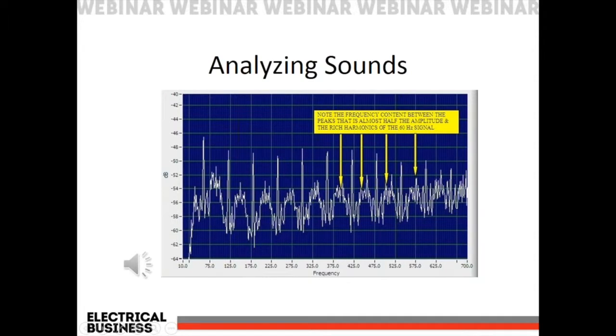Now, I hope that came through clearly, but it was a very obvious, consistent frying bacon sound that's being heard there. And when we record this on our instruments, we bring it back into a spectral analysis, in this case an FFT, or fast Fourier transform for the long version. What we're seeing here is obviously a distinct 60 Hertz harmonic. However, just because it's 60 Hertz doesn't necessarily mean it's corona, and it doesn't even necessarily mean it's an electrical emission. It's just saying that 60 Hertz is present there.